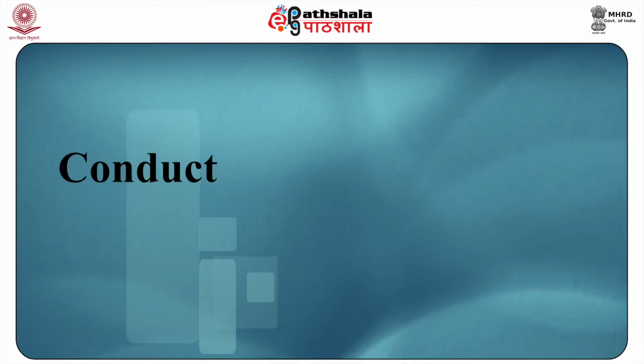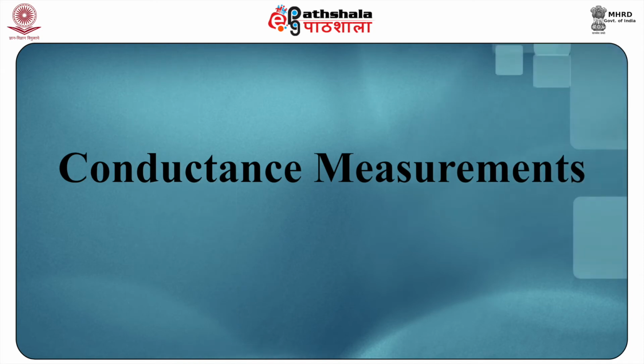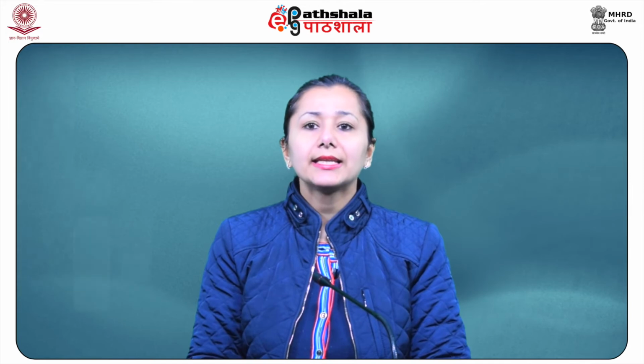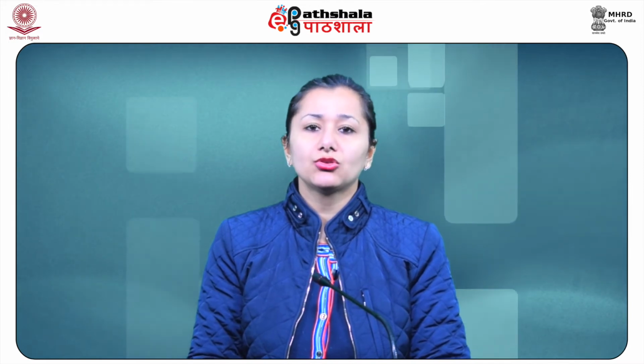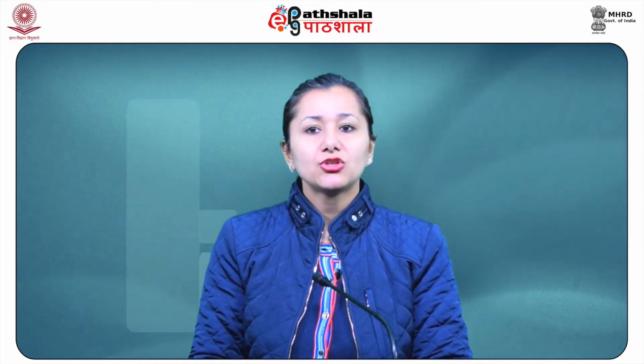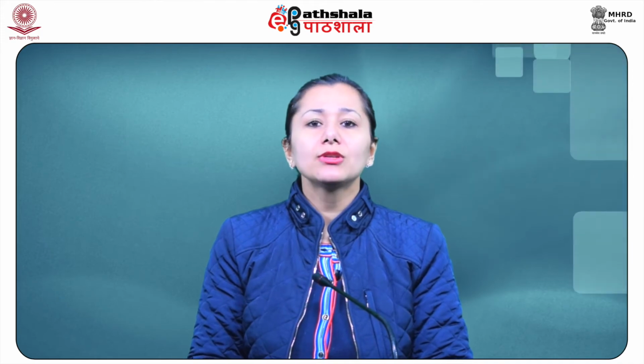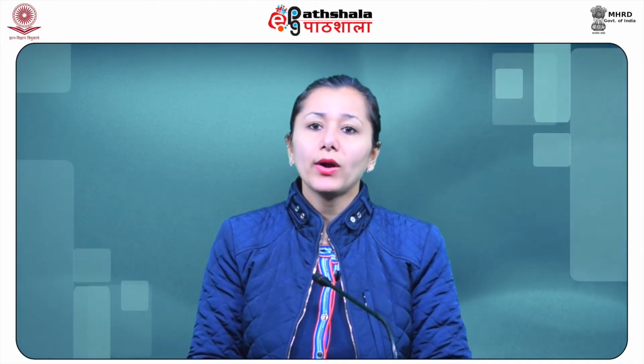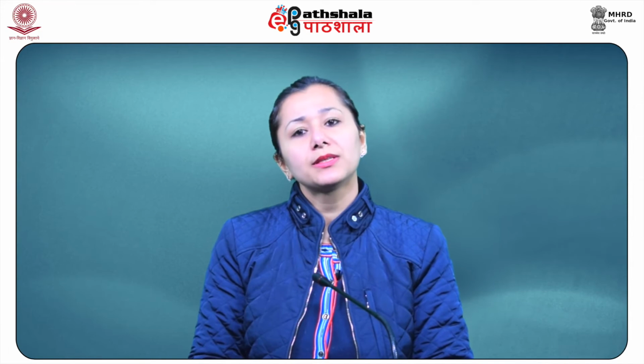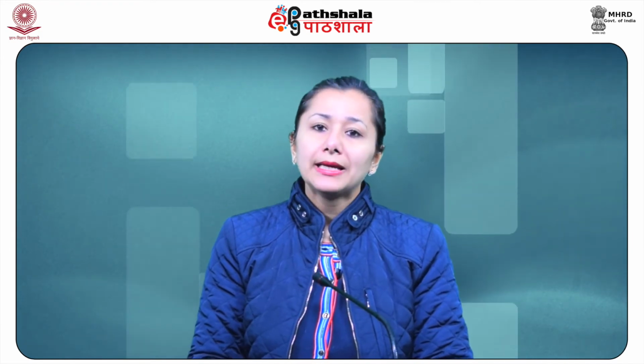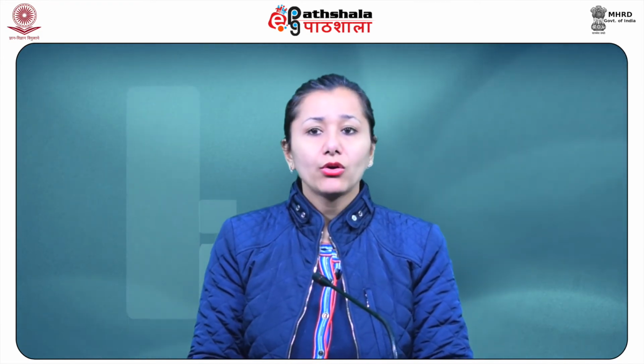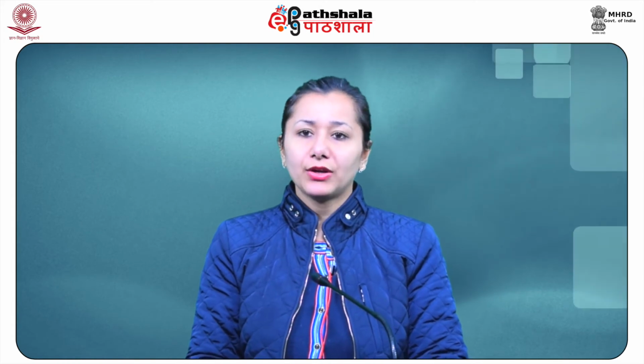Now, we shall talk about the conductance measurements. In conductometric measurements, the electrodes are placed in intimate contact with the solution and an alternating potential is applied. Polarization at the surface of these electrodes is avoided by increasing the macroscopic surface area through platinization and/or operation at sufficiently high frequency.